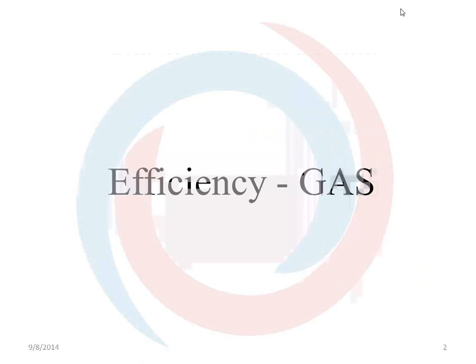If you put two of them together, you can see what happens is you have 1700 degrees at the inlet and about 400 degrees at the outlet. Being non-condensing, 400 degrees is pretty typical across the industry. But unfortunately, when you have two in series, you start out with 80% efficient on the first one, but you don't end up with 80% efficient on the second one. And this is fine per ANSI standard 83.8. It only requires you to test one furnace at a time. It doesn't require you to test two furnaces in sequence. So you can see that the second furnace is losing 5 to 6% efficiency, mostly because of the higher entering air temperatures on the secondary heat exchanger. If you can imagine 3 heat exchangers, or 1.2 million, you're down around 70% efficiency.